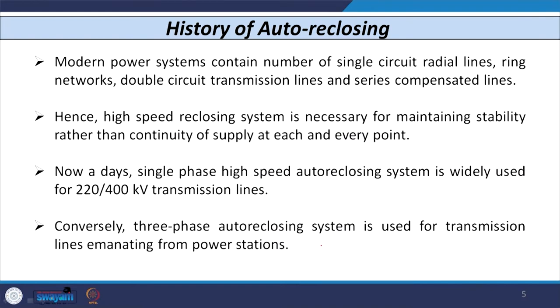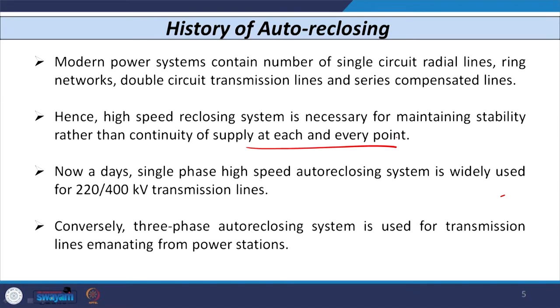Modern power systems contain radial lines, ring networks, and double circuit and series compensated lines. High speed reclosing is necessary to maintain stability rather than just continuity of supply at each point. Nowadays, high-speed auto reclosers are being utilized particularly for 220 kV and 400 kV EHV and UHV lines, while three-phase auto reclosing is used for transmission lines emanating from substations.